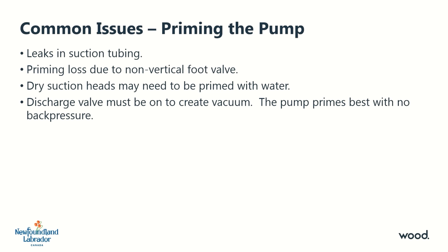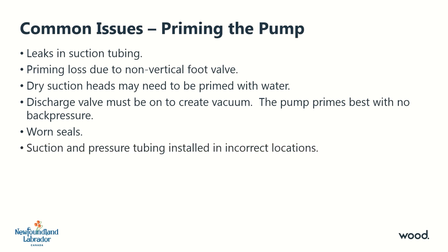Other issues that can be encountered that will impact the operation of the chemical feed pump include worn seals which require replacement, suction or pressure tubing installed at incorrect locations, and clogged injector fittings. This can be a problem where systems have elevated turbidity, or it could be caused by deposits from the water.